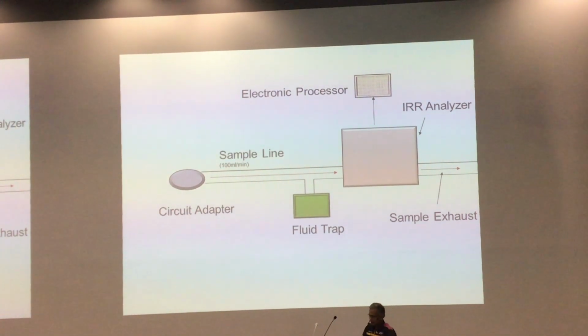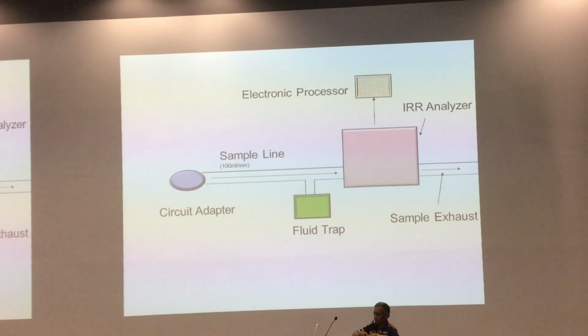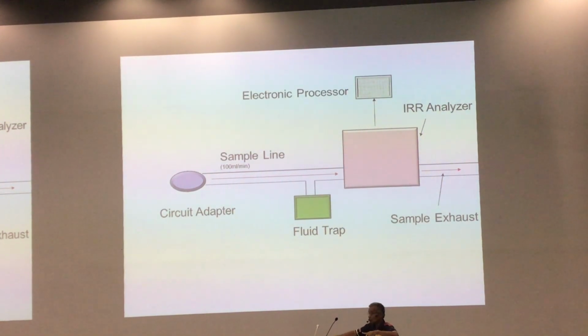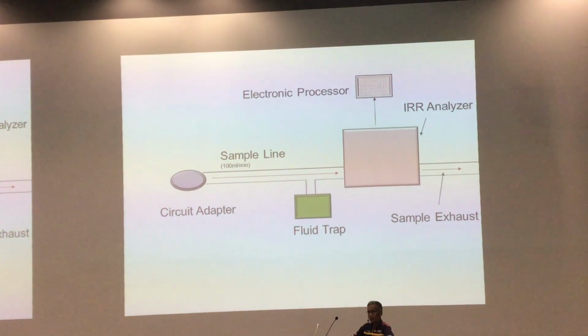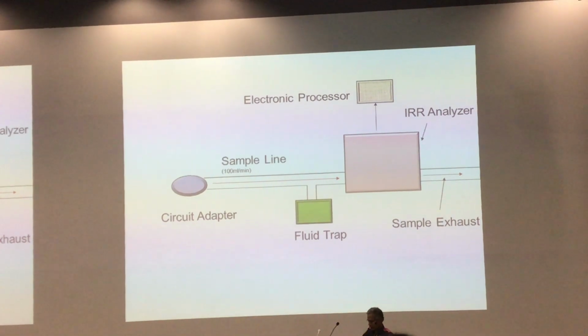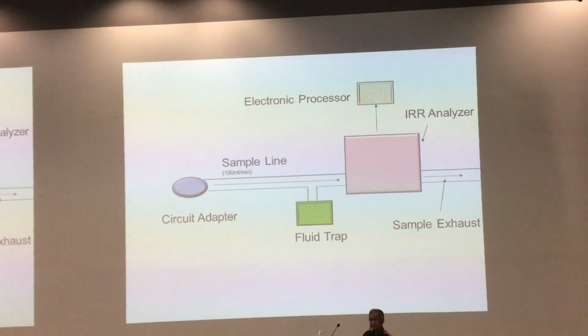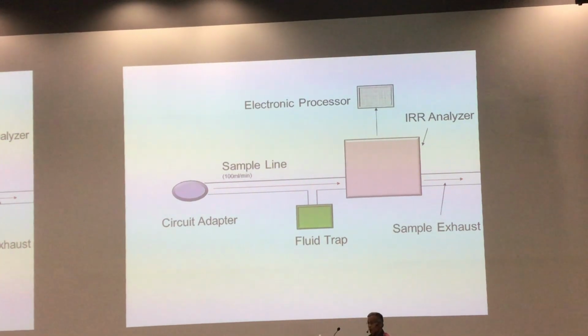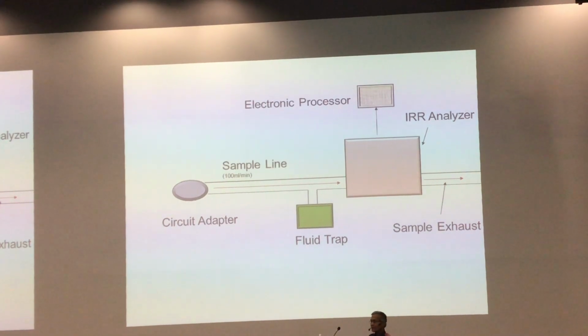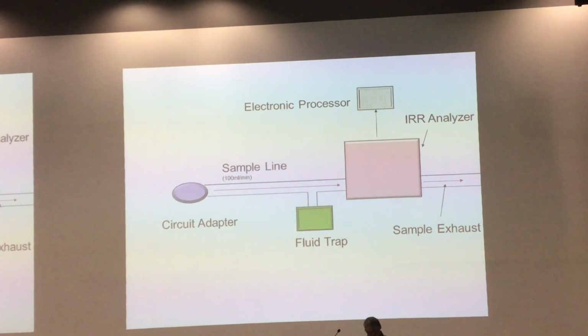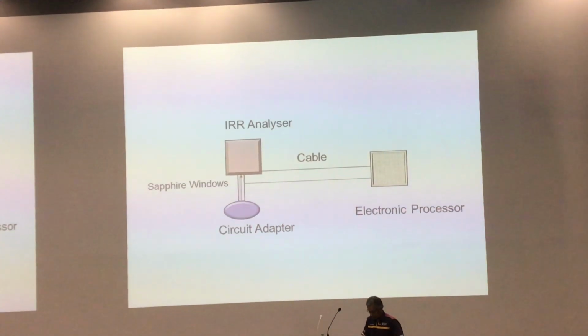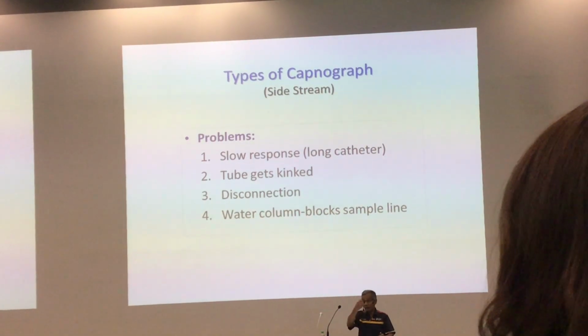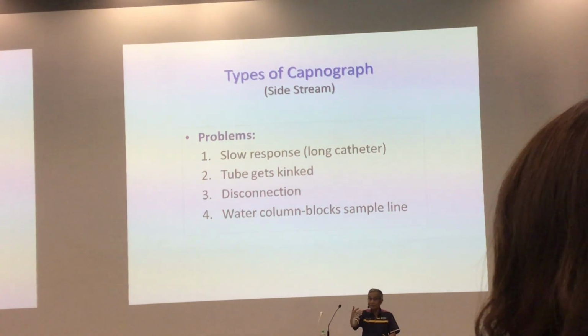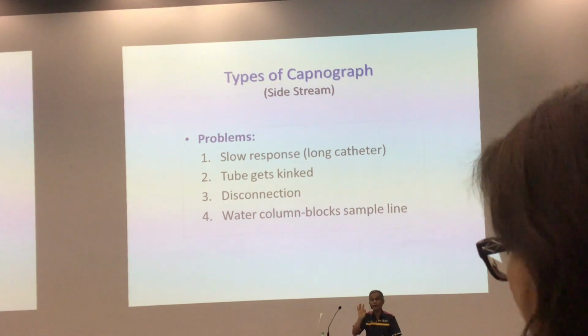Side stream sampling means there's a sample line from the Y-piece, right, to the CO2 module. About how many meters? About 1 meter. The sampling line is attached to the Y-piece and goes to the CO2 module in the machine, and it will analyze the CO2 content in that specific gas using an infrared analyzer. Because of the long tubing, it gets a slow response to get the capnograph. After you have intubated the patient, right, it takes maybe 30 seconds to get the waveform. So there's a slow response using this technique.